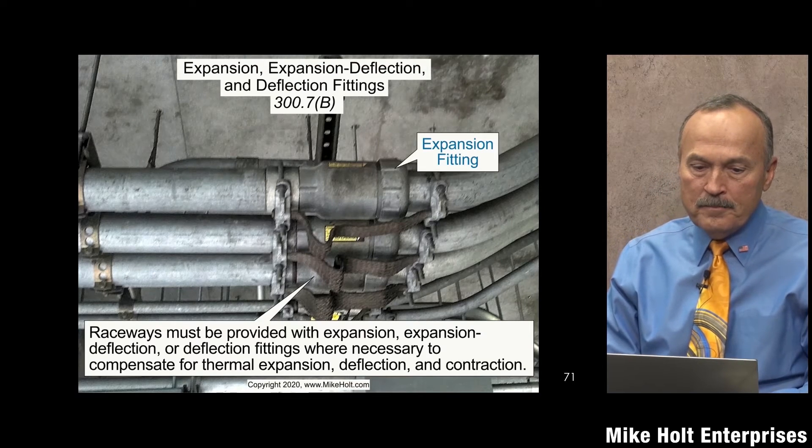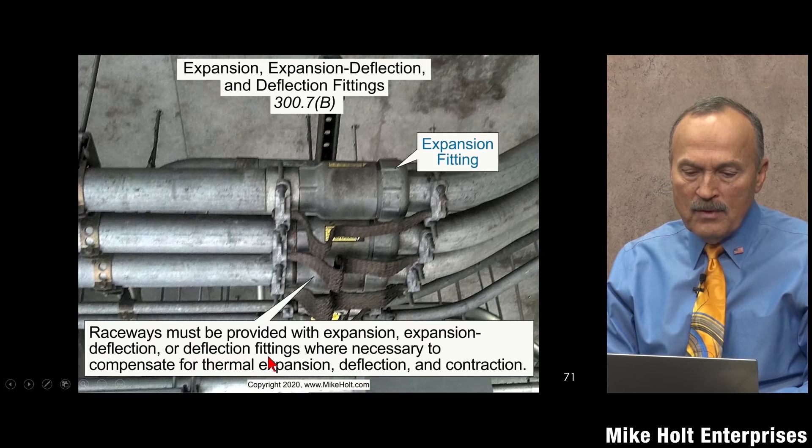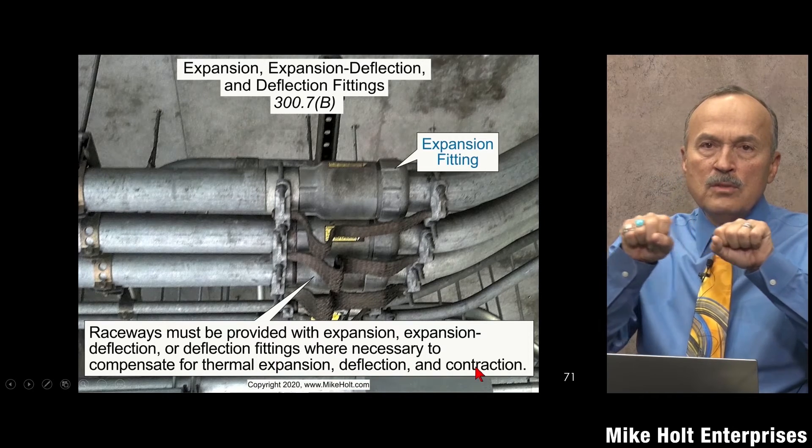Expansion fittings. Raceways must be provided with expansion, expansion-deflection, or deflection fittings where necessary to compensate for thermal expansion, deflection, or contraction. This fitting right here is only for expansion — it only goes this way. But they make fittings that are designed for deflection as well.